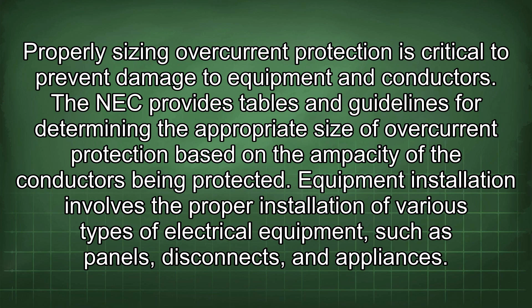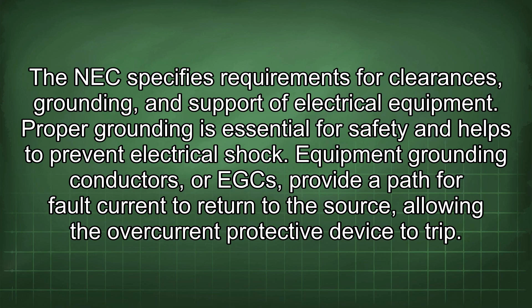Equipment installation involves the proper installation of various types of electrical equipment, such as panels, disconnects, and appliances. The NEC specifies requirements for clearances, grounding, and support of electrical equipment. Proper grounding is essential for safety and helps to prevent electrical shock. Equipment grounding conductors, or EGCs, provide a path for fault current to return to the source, allowing the overcurrent protective device to trip.